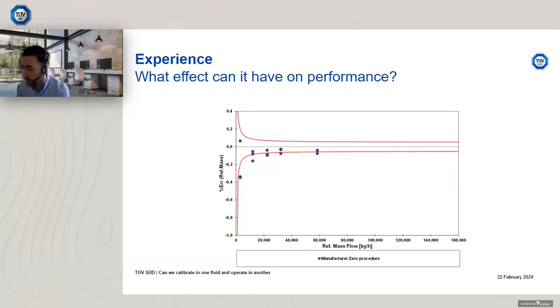I then followed the manufacturer zero procedure, and for this installation, it might not have been optimum installation, but you can see that some of the data was within specification. The zero was okay, maybe wasn't perfect. I just wanted to show you that even if you follow the manufacturer zero procedure, it doesn't mean you're always going to get a perfect zero. There could be other factors influencing the performance of that Coriolis meter.